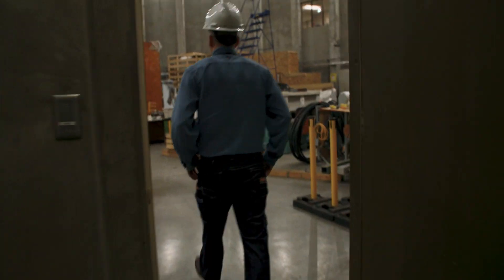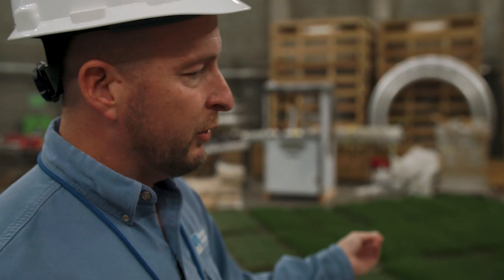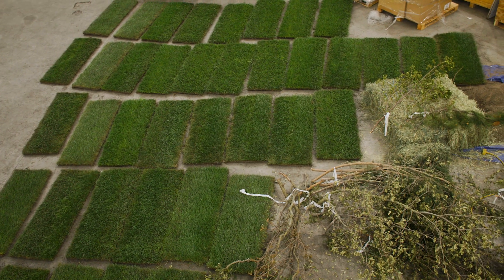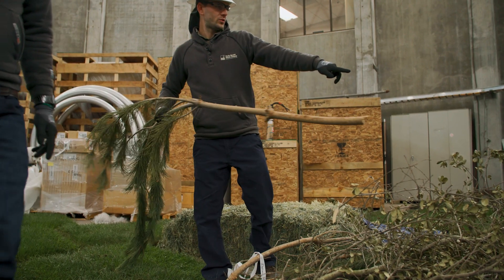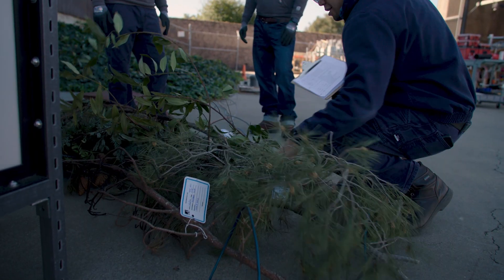The testing we've been doing involves ignition testing. One thing we'll do is purchase sod, dry it to a specific moisture content, and then run tests on it. The sod we have here hasn't been dried yet. We'll also collect vegetation — the intent is we're experimenting with different fuel medias in our tests.